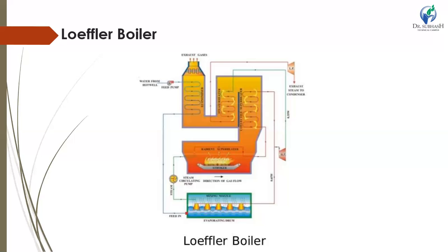About 35% of the superheated steam from the convective superheater passes through the steam turbine to develop mechanical work, while 65% is passed to the evaporative drum to evaporate feed water into saturated steam. The amount of steam generated in the evaporative drum is equal to the steam tapped, around 65%, from the convective superheater.